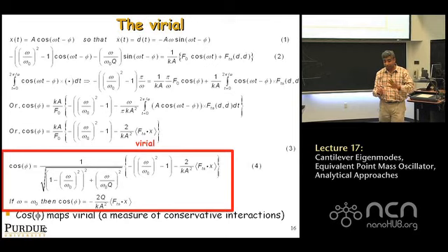If you plot sine of phase, what you're doing is measuring energy dissipation. If you plot cosine of phase, you're actually plotting a measure of conservative interactions, Van der Waals forces, elasticity, etc. Hardly anyone makes this distinction, but it's very important. Not surprisingly, if you get a contrast in phase, if the value of phi changes over the sample, obviously sine of phi and cosine of phi are also going to change over the sample. Okay?